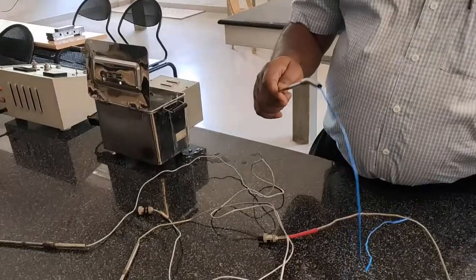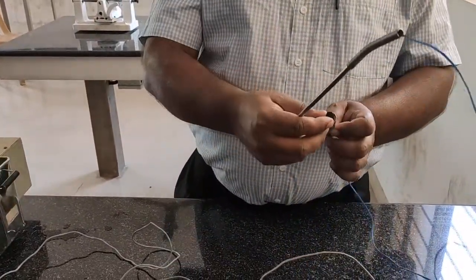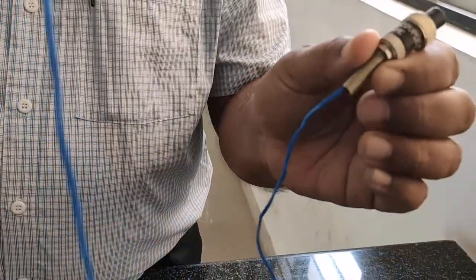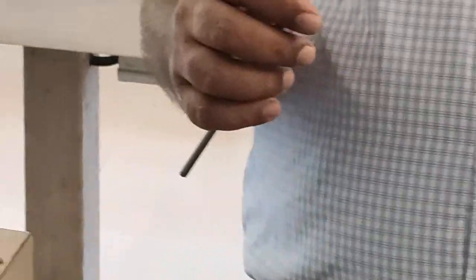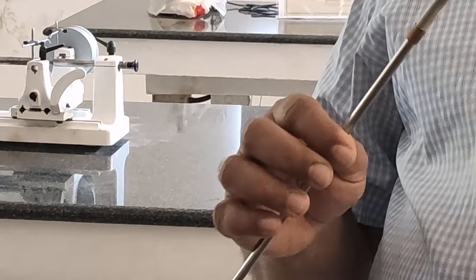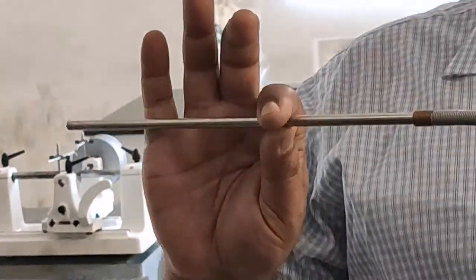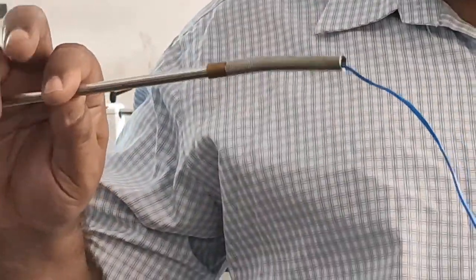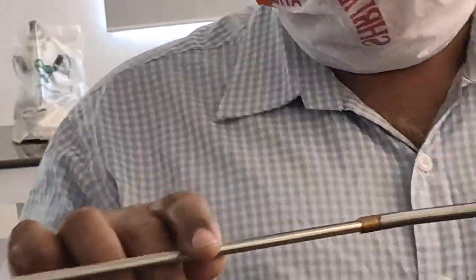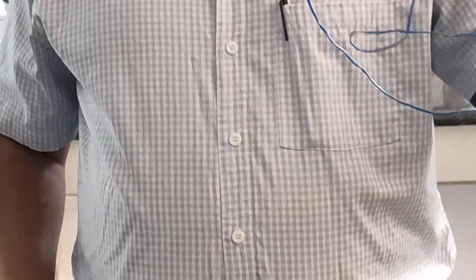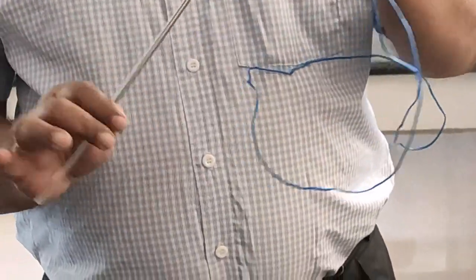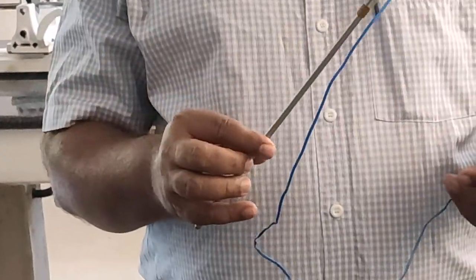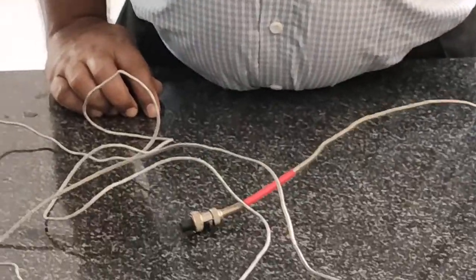Now let us know what kind of thermocouples these are. This is what we call the T-type thermocouple, with a color coding of blue cable. This T-type thermocouple is called constantan thermocouple, and it measures a range of minus 250 degrees to 400 degrees centigrade. It can't be used beyond 400 degrees centigrade. One more concern when using thermocouples in a hot molten metal bath is that you should not expose them immediately to the open air. If exposed immediately, it will lose its precision in measuring temperature. It should not be oxidized.